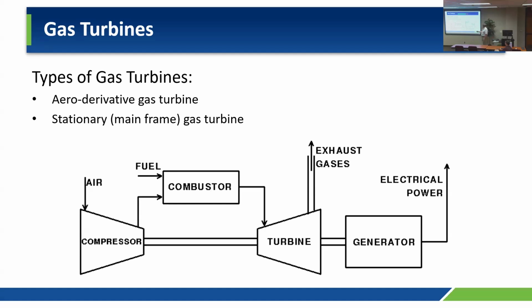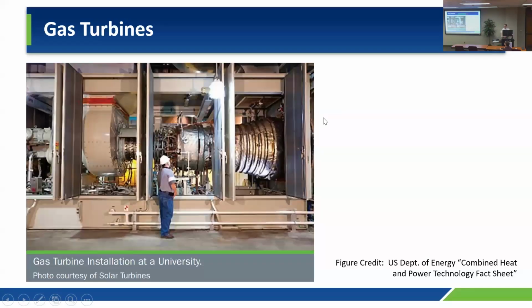Essentially what you do is bring in air through a compressor, send that compressed air into a combustor with your natural gas fuel, and combust it, which drives a turbine. Some of that turbine work drives the shaft that drives the original compressor, and the rest goes to an electric generator that gives you electrical power. What comes out of the turbine is exhaust gases containing a lot of heat energy, and that's where we recover heat from. So we generate both electricity and heat that we can use for our processes.